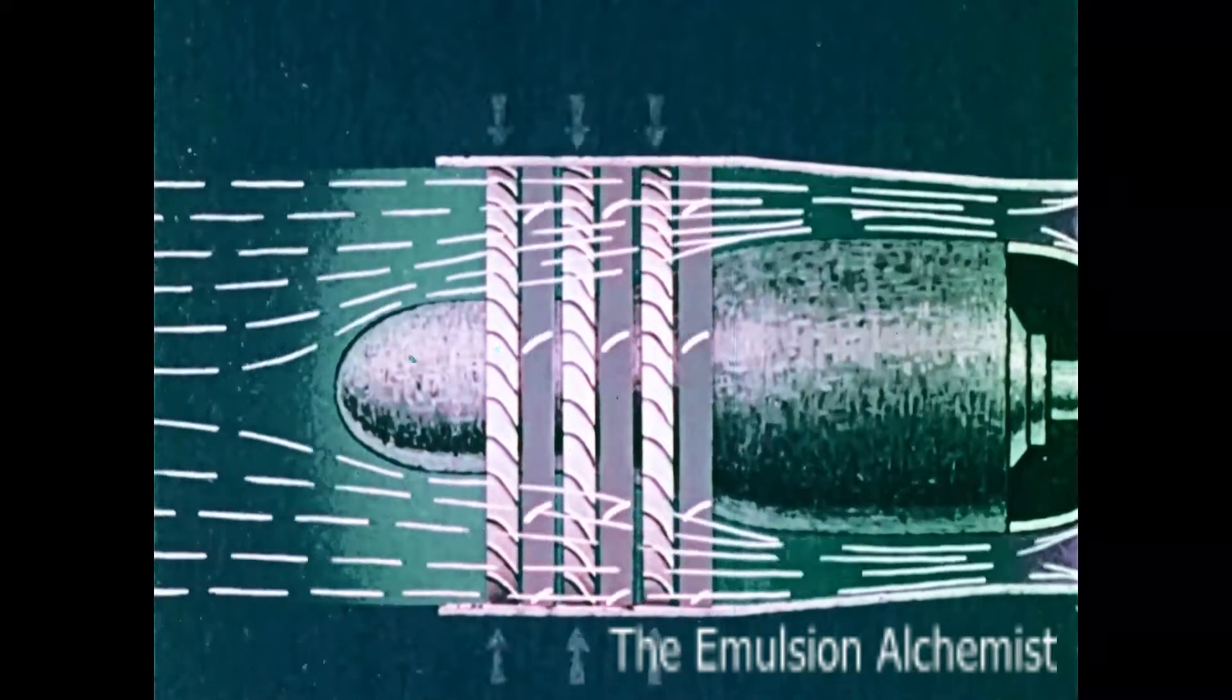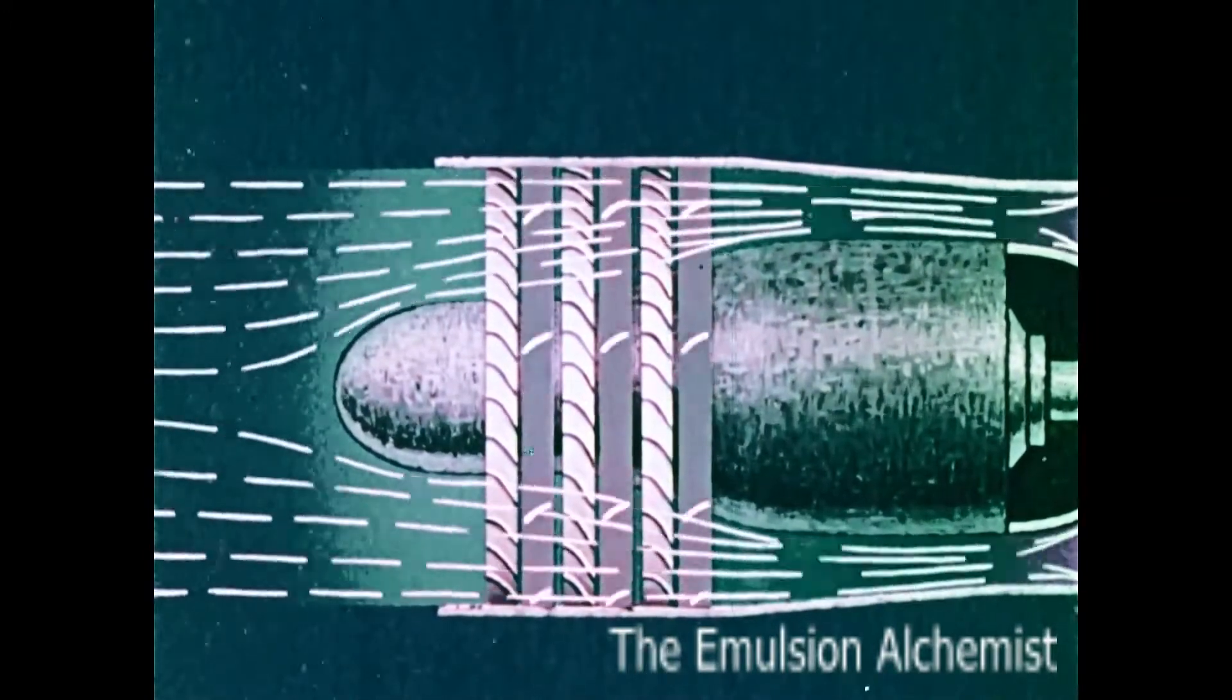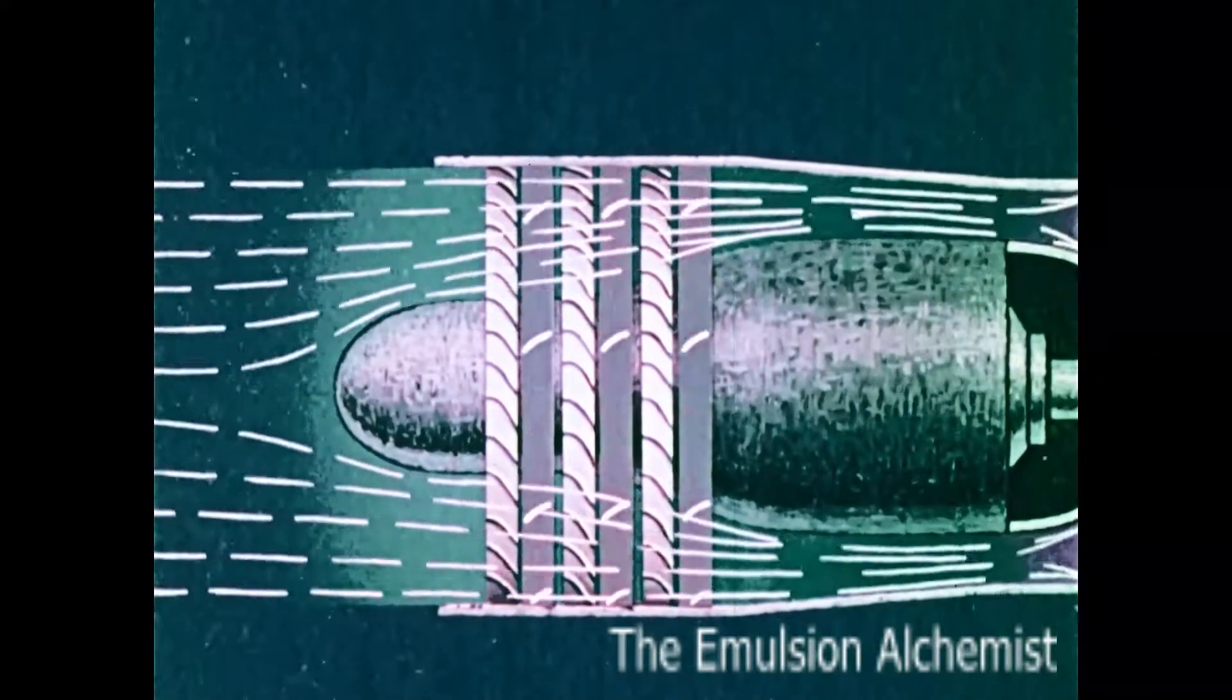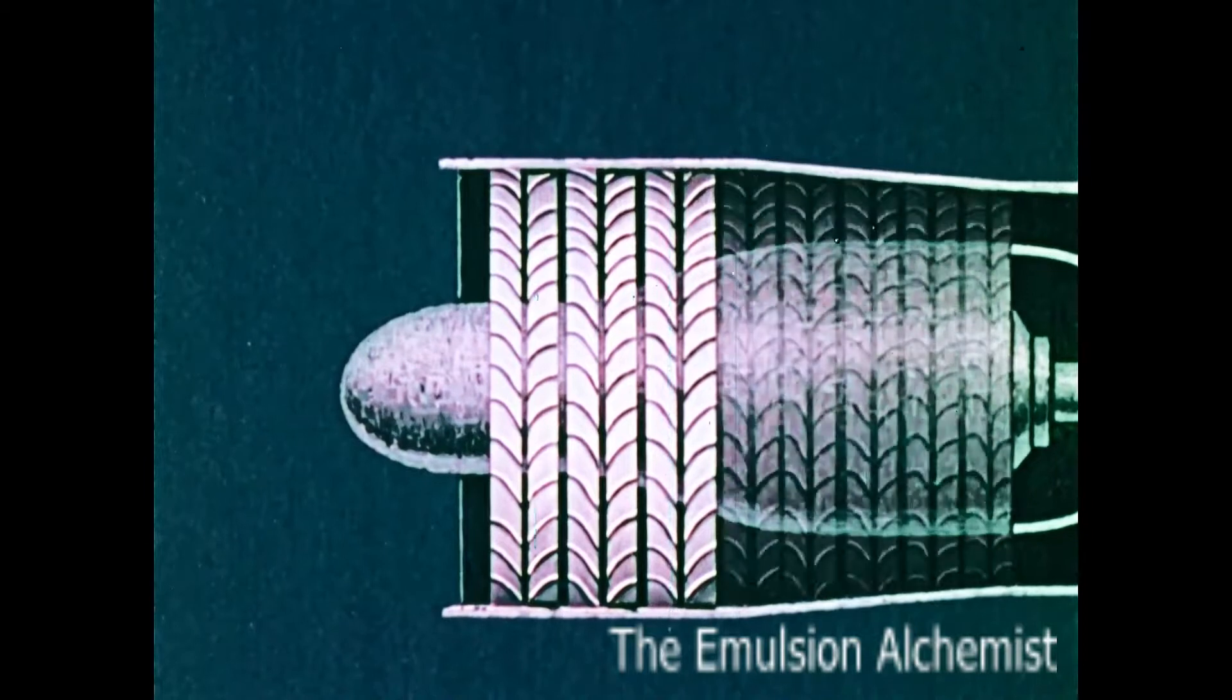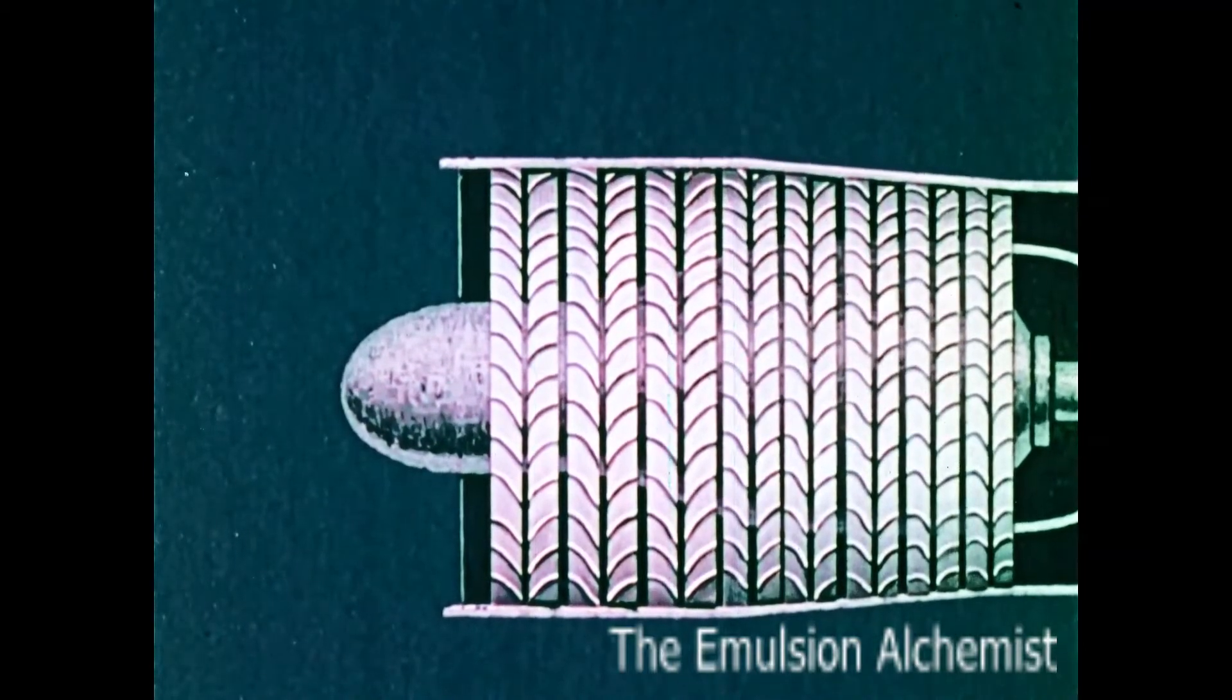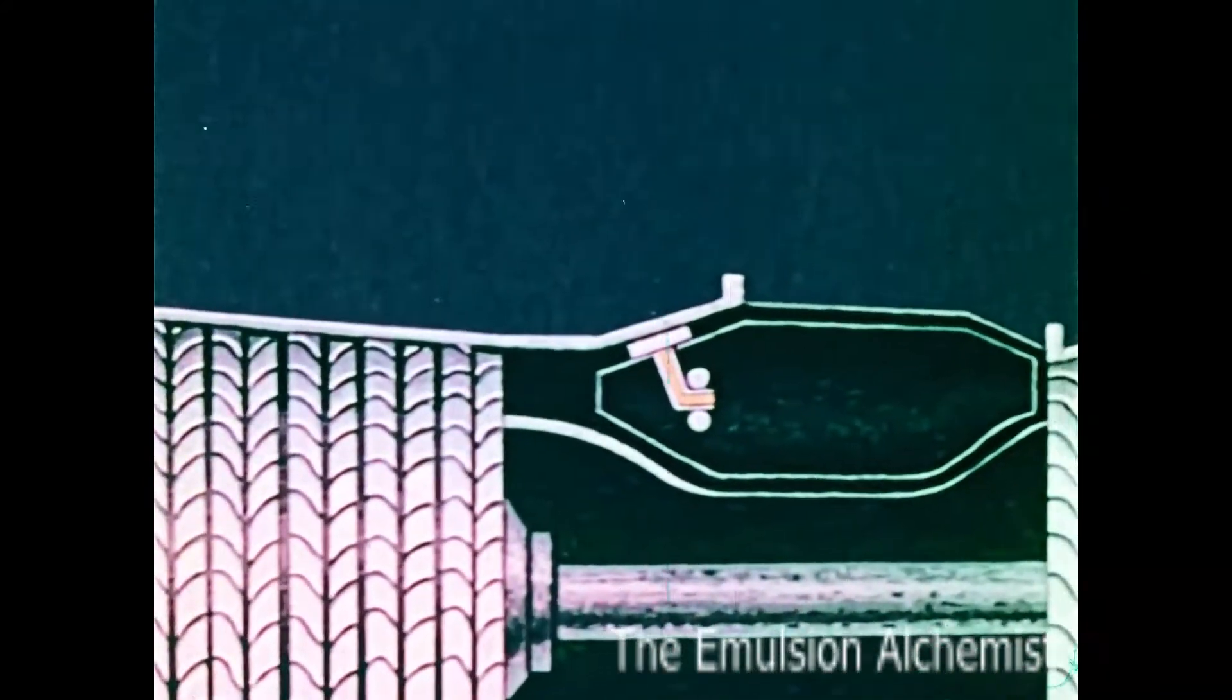The compressor also has stationary blades. They decrease the air's velocity, raising its pressure. Axial type compressors usually have several stages. They add more pressure to the air, which is then directed into the combustion chamber.